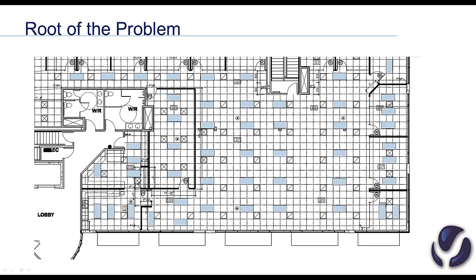When the electrician first wired this floor, he installed a breaker panel on the wall here. He then pulled an MC cable up out of the top of the panel and ran his circuit across the floor, picking up lighting loads along the way. He ends the circuit in this office here. So let's talk about this zone as an example. The electrician might have brought a power and neutral into the wall box location and then pulled another wire up out of the top of the wall box called the switch leg to the fixture. Remember, this wire here is called the switch leg. The switching location is in the wall as it is in all buildings.